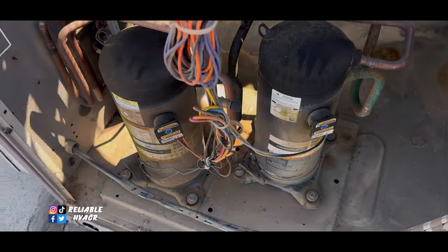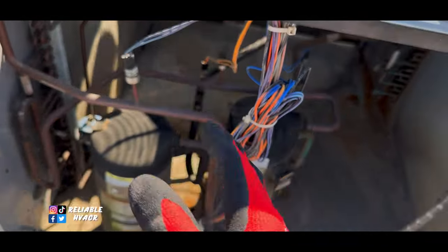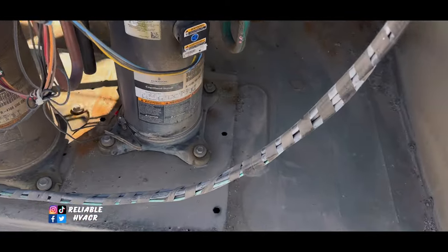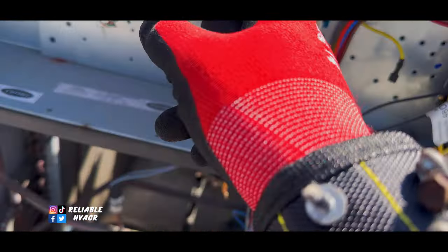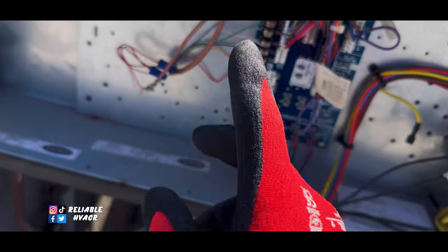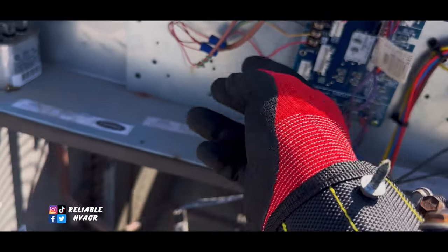And then, we'll bypass everything up here. And then, what's going to end up happening is probably just the thermostat gave out. Because we do have 24 volts. It doesn't take batteries or anything. It's just the 24 volts here. It should be supplying it.